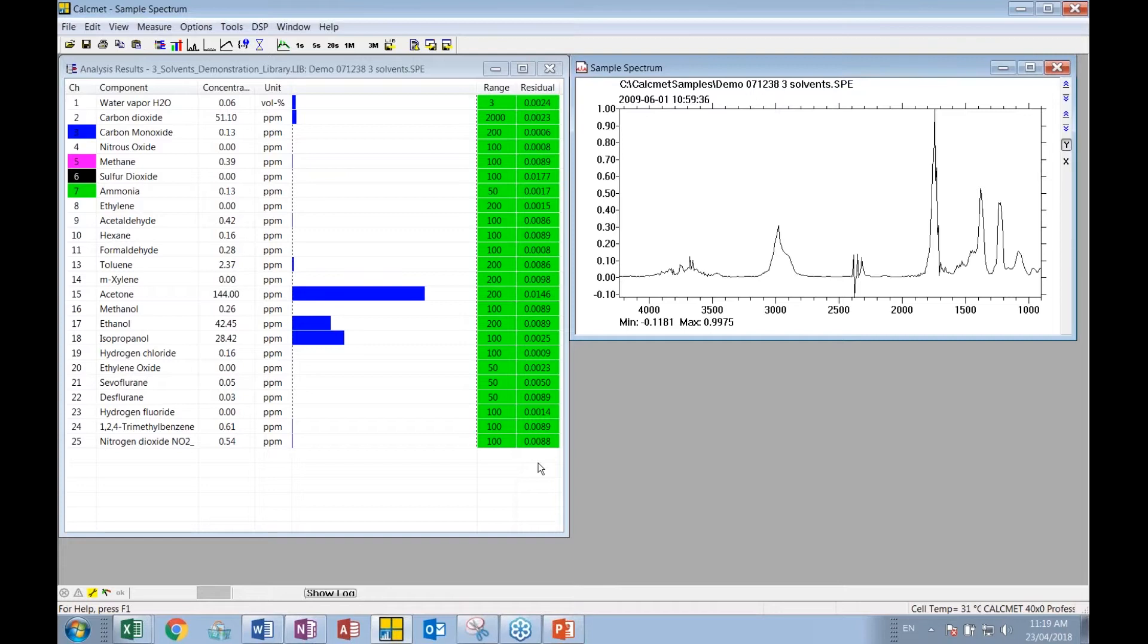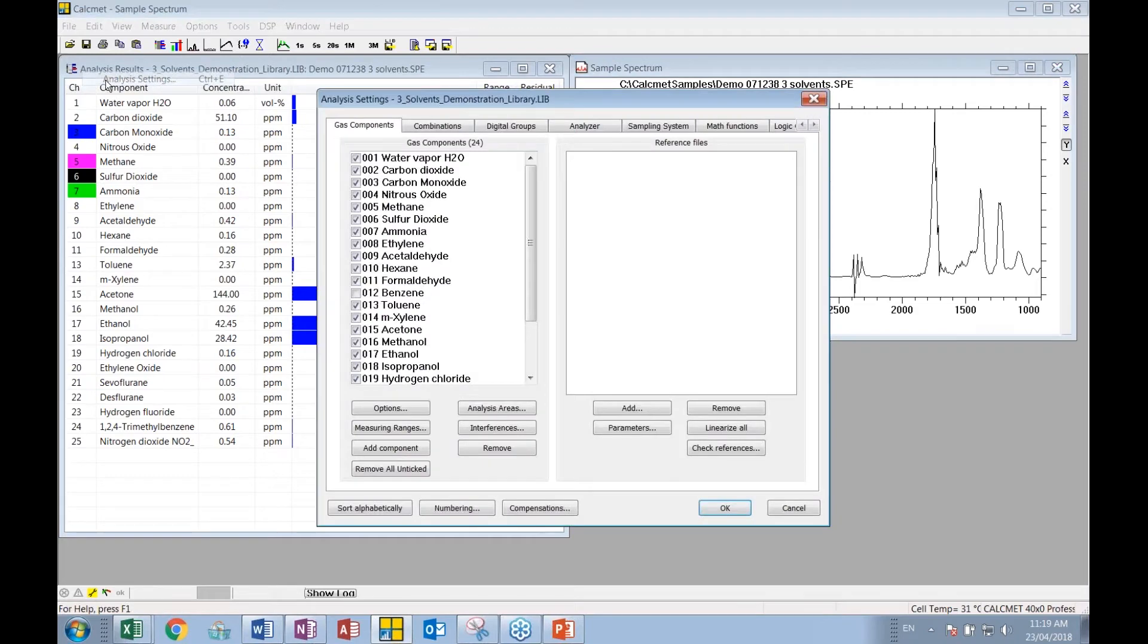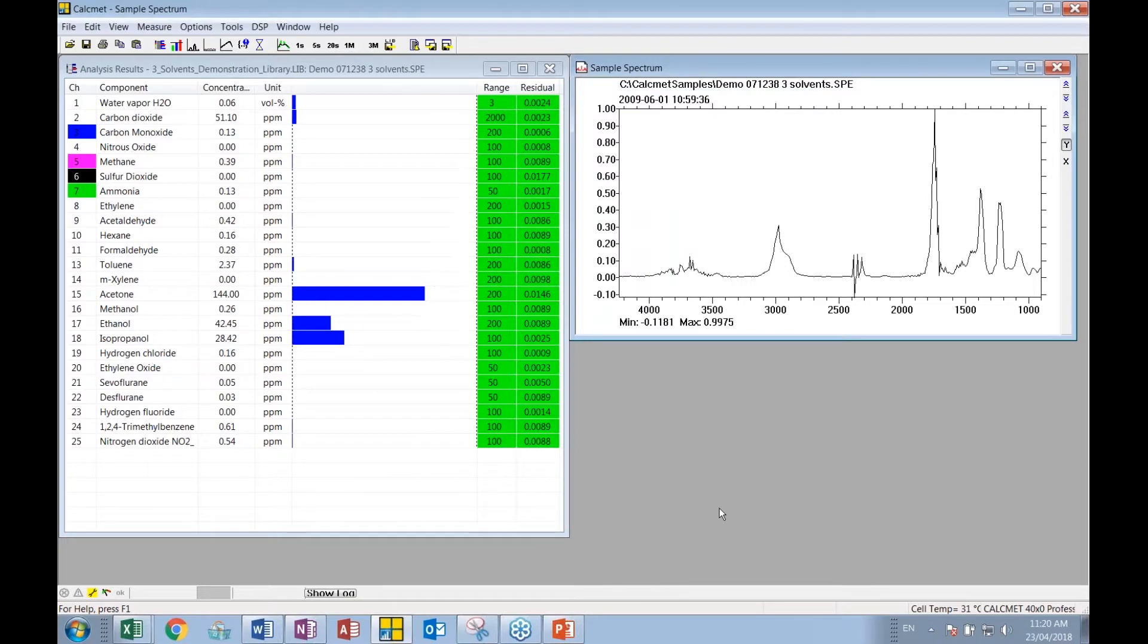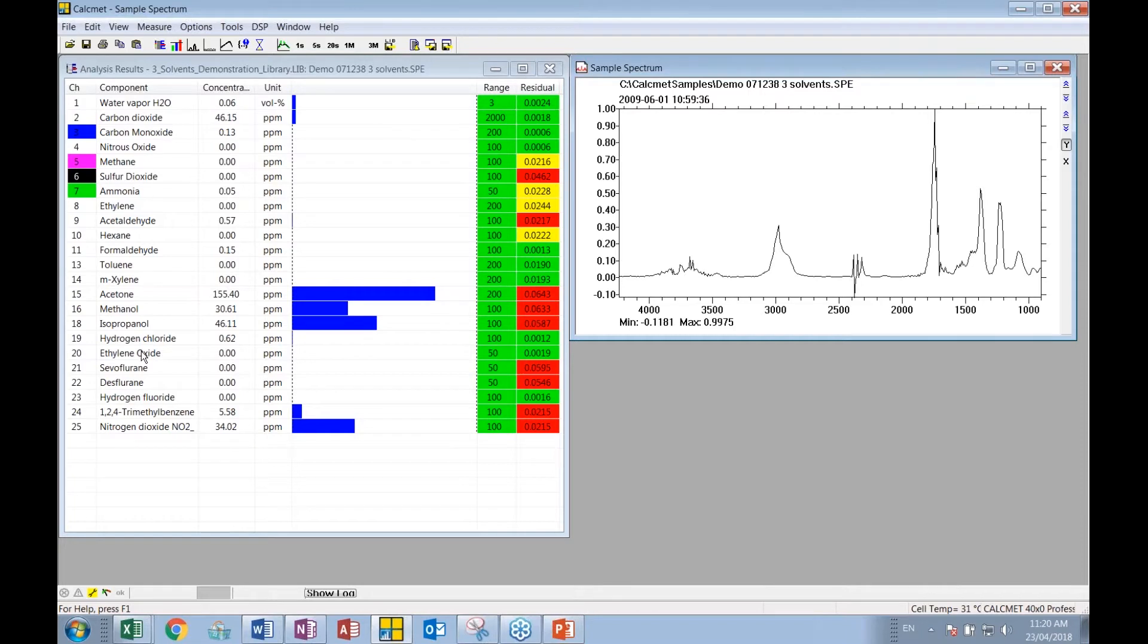So here's the signal of an unknown. So what I'm about to do is take one of these gases out, and it doesn't matter which one it is, but let me say that I'm going to take the ethanol out. Then what has happened is it's been a reanalysis. Same sample, of course, we have still got the complete sample, but now the application library is devoid of one of the main components, which is the ethanol.